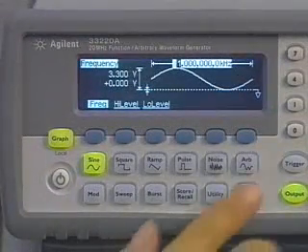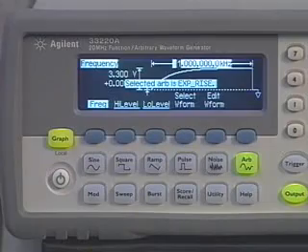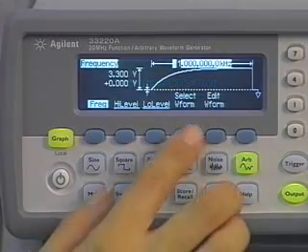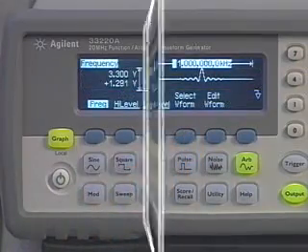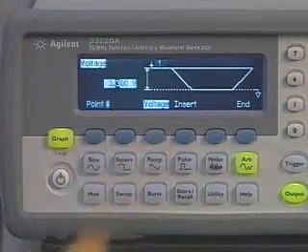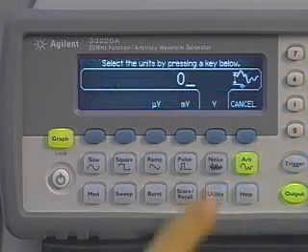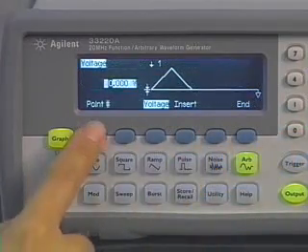The 33220A comes with five preloaded arbitrary waveforms. Four non-volatile and one-volatile memory locations are available for user-defined waveforms. Each user-defined waveform can contain between two points and 65,536 points.